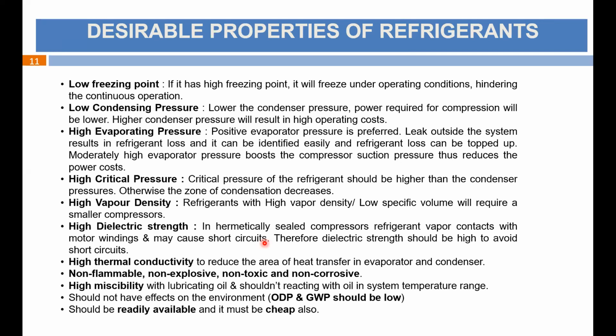Critical pressure, as you know, is a pressure above which, even if you pressurize the refrigerant, it cannot be condensed, or it cannot be changed from the vapor to the liquid stage. So the critical pressure of the refrigerant should be higher than the condenser pressure. If it is lower than the condenser pressure, like we often encounter this problem with CO2, carbon dioxide, because CO2 has only a 31 degrees centigrade critical temperature. In that case, a different type of system is adopted, but there should be high critical pressure so that the zone of condensation doesn't decrease.